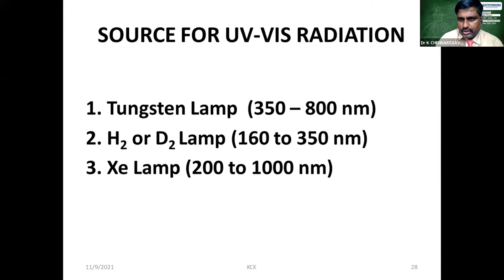And the block diagram of UV visible spectroscopy is this. See, the light source will be there and the monochromator will be there, and the monochromator will give monochromatic radiation, and the monochromatic radiation will interact with our sample. See the light green color, which is in a glass cuvette or quartz cuvette. Cuvette is nothing but a sample container, which is made of either glass or quartz. If you are going for UV, we use quartz. If you are going for visible, you use glass.